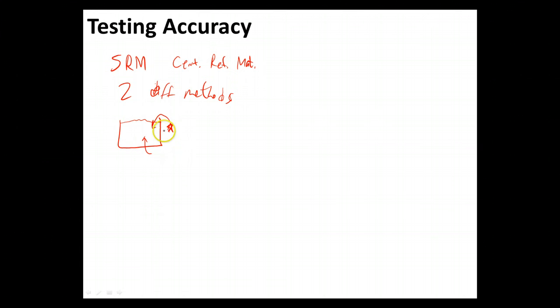We want to go over a pretty good range there, though. We want to go from about half the concentration to about 1.5 times the concentration that we were expecting, because you never know exactly where it's going to be. And don't forget, there's some techniques like spectroscopy where there's a linear range, but then your detector maxes out and you can't see anything above it. So we need to do this to make sure that we don't end up with our measurements way out here. So if we're expecting our value to be about here, we'll do a measurement here, and we'll do a measurement here where we've made up our own concentrations.